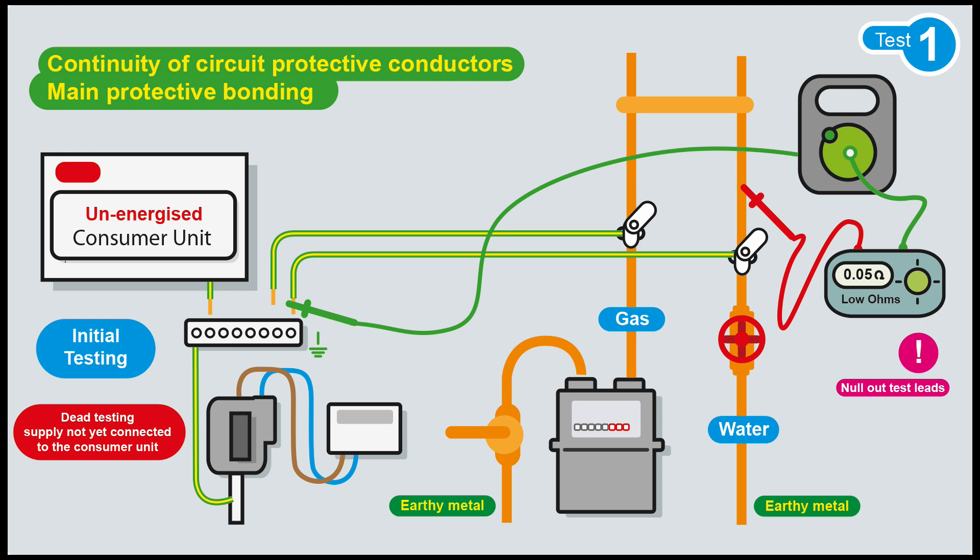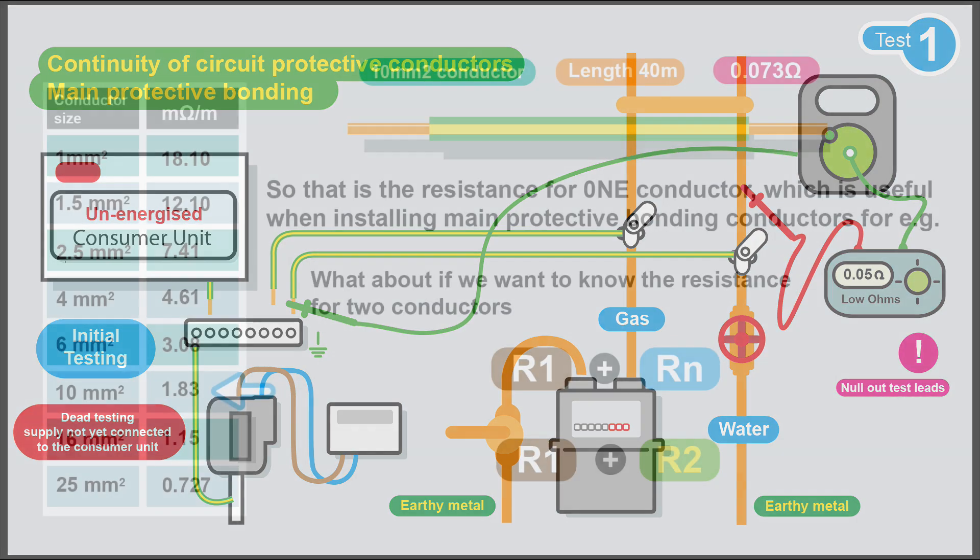For our main bonding conductors, we might have to consider going to a larger size. We'll do this later, but you can actually transpose the formula and work out from 0.05 ohms how many meters that is. I'll tell you it's 27.32 meters, but we'll do that in a bit.